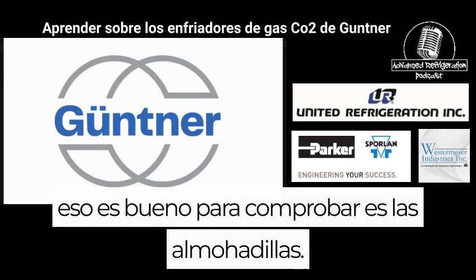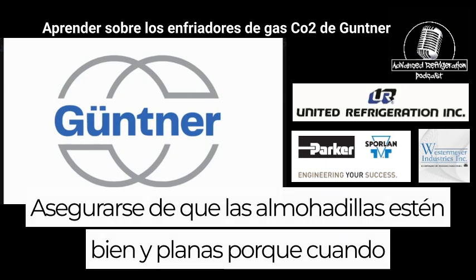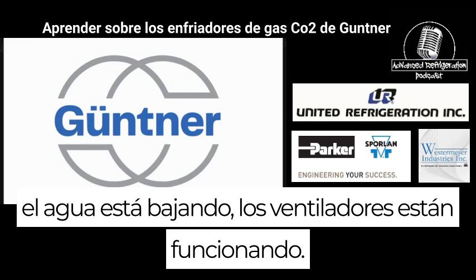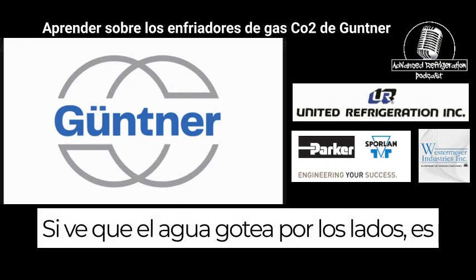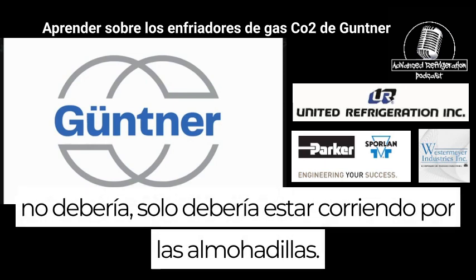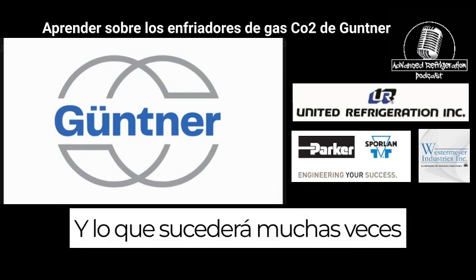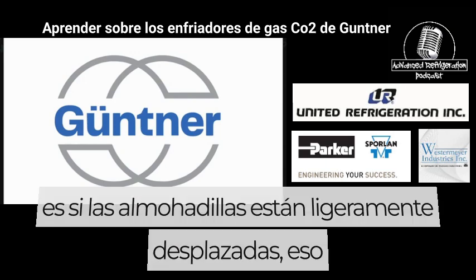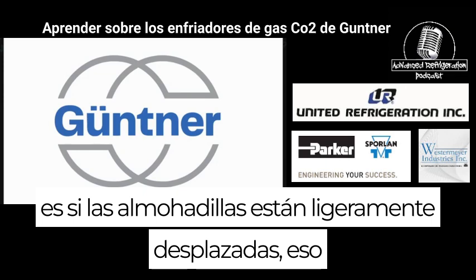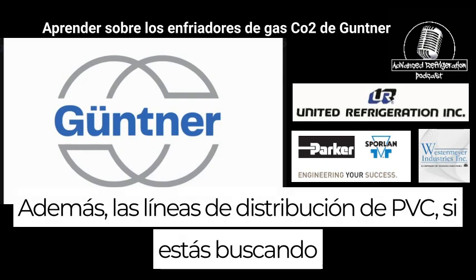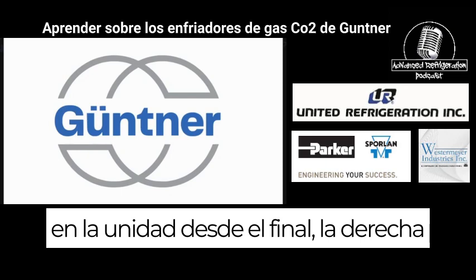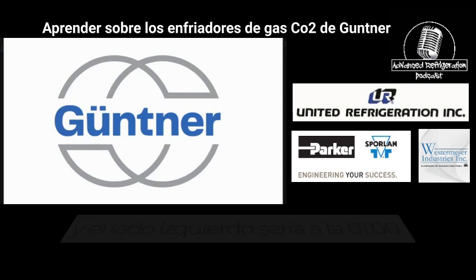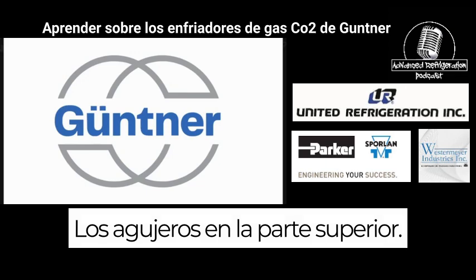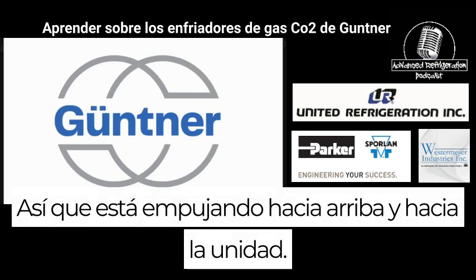One of the things that's nice to check is the pads, making sure the pads are nice and flat, because when the water's coming down and the fans are running, if you see the water dripping off the sides, it should just be running down the pads. What'll happen a lot of times is if the pads are offset slightly instead of being flat, that can cause the dripping. Also, the PVC distribution lines: if you're looking at the unit from the end, the right side should be facing up and towards. So the right side would be at 11 o'clock and the left side would be at 1 o'clock, with the holes on the top, so that it's pushing up and towards the unit.